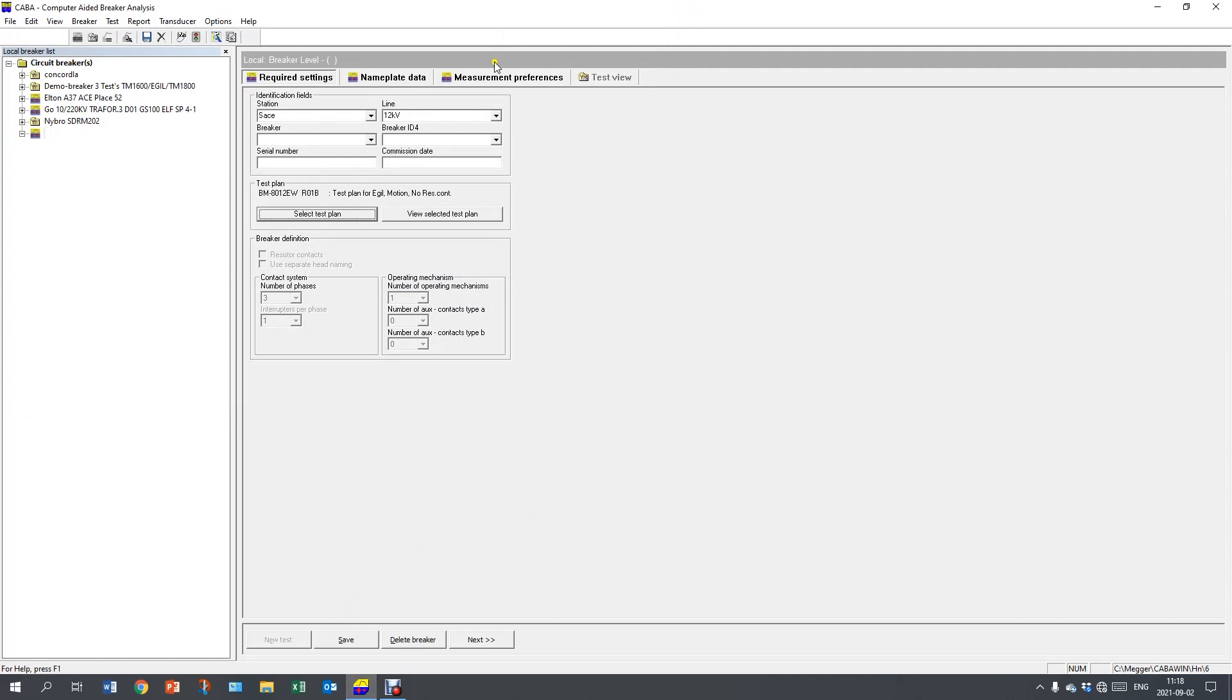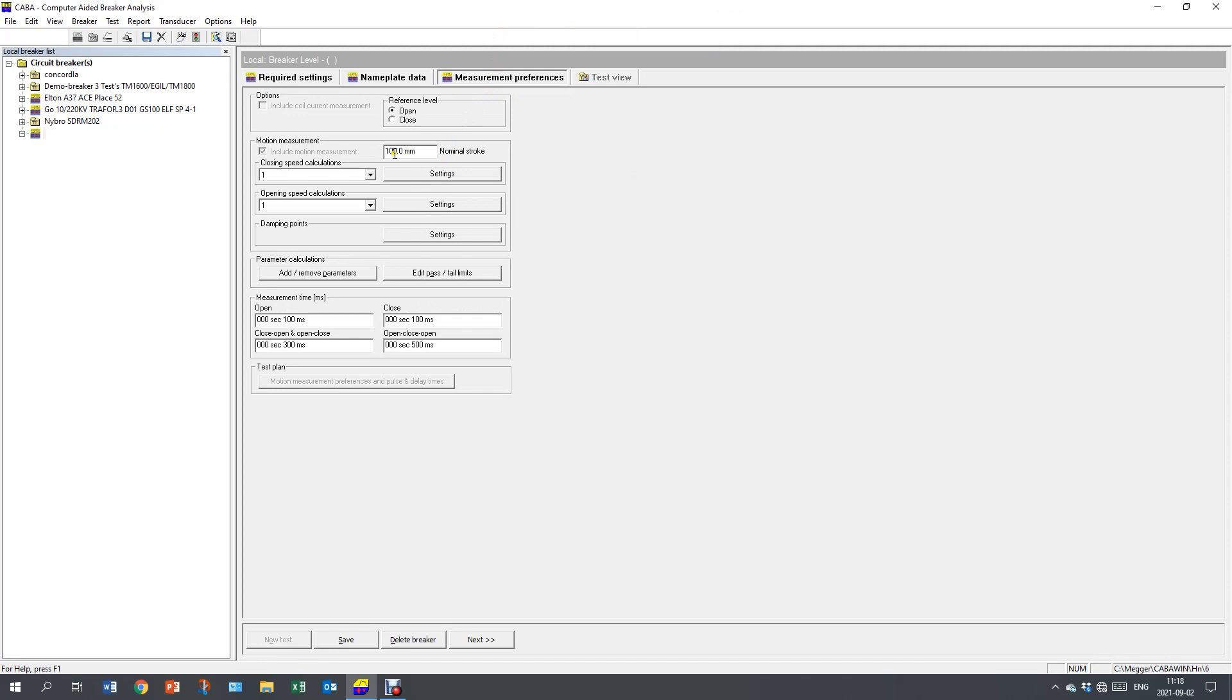I continue with setting the stroke. I use 100 mm because I don't know the stroke of this transducer. So I use a simple value as 100 because it's easier to calculate if I get more information in the future. I extend the measurement time on both close and open operation. I know this breaker is slow and I need enough time to catch the whole motion, not only the timing. I save. And now I have my new object in the list.